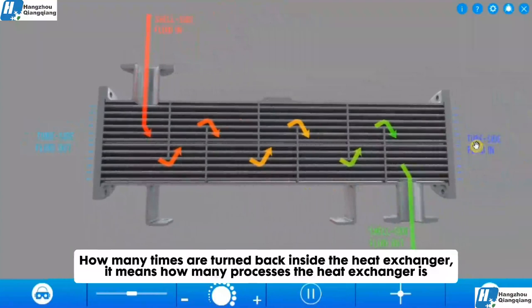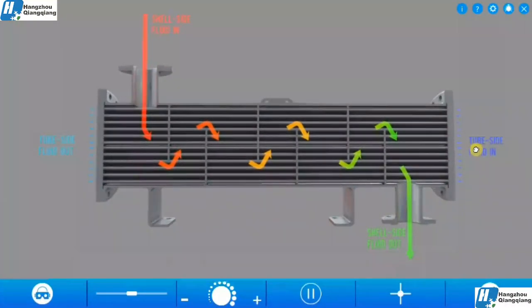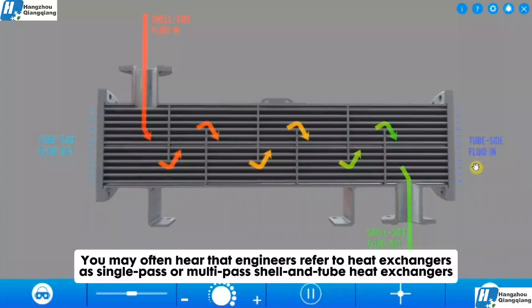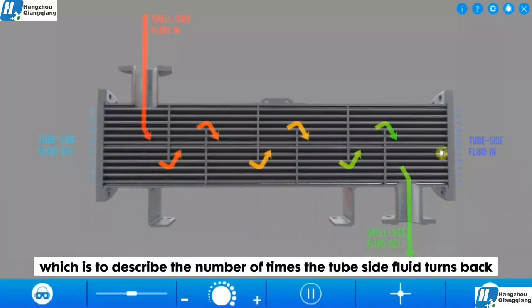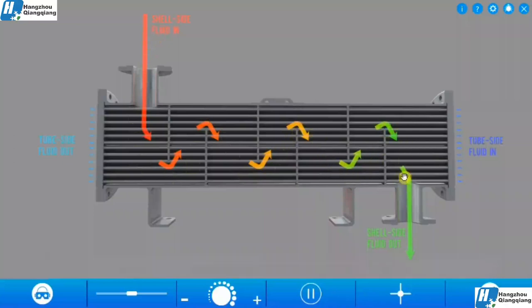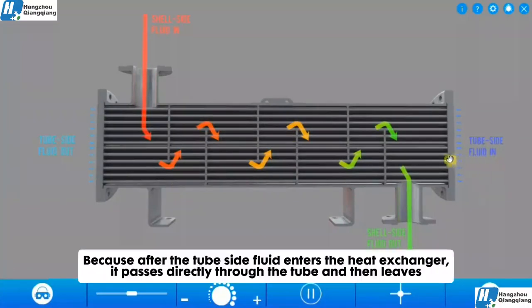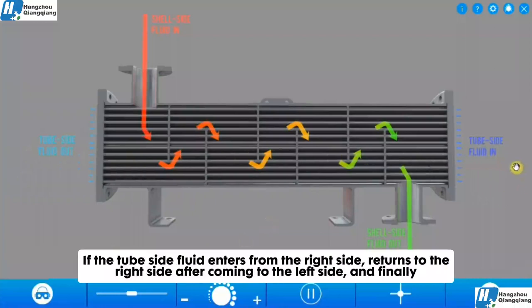How many times the fluid turns back inside the heat exchanger describes how many passes the heat exchanger has. You may often hear engineers refer to heat exchangers as single-pass or multi-pass shell and tube heat exchangers, which describes the number of times the tube side fluid turns back. The shell side fluid passes through baffles to realize multiple return. The shell and tube heat exchanger we see now is a single pass, because after the tube side fluid enters, it passes directly through the tube and then leaves. If the tube side fluid enters from the right side and returns to the right side after reaching the left side, that is a multi-pass design.